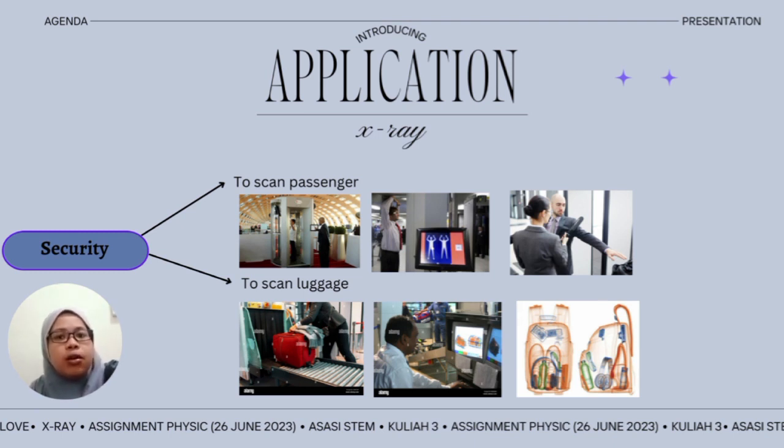A computer compares the data yielded by the two detectors to better depict low energy items such as biological items. Since different objects absorb different amounts of X-ray, this difference can be seen on the screen used by the operator. There are three primary categories depending on the spectrum of energy that pass through the object, like organic, inorganic, and metal.